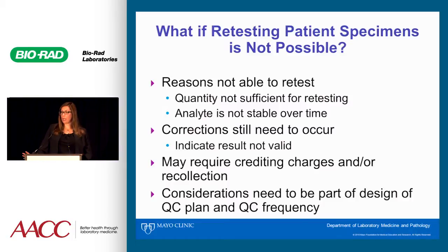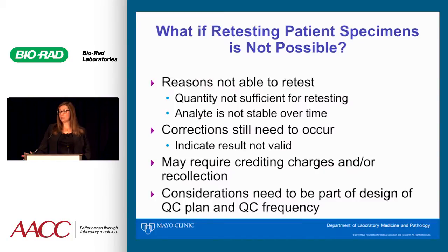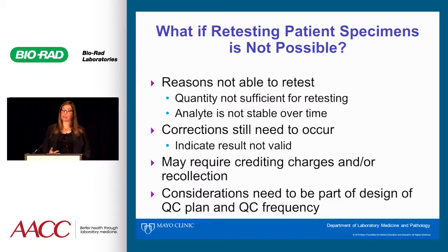I also oversee coagulation. We have a few analytes in general COAG where samples are only stable for four hours. They're pretty low-volume tests, but we need to factor in that our QC should probably be done at a frequency of every three hours, so we don't run into a problem where a sample has expired, we then catch an analytic issue, and there's nothing we can do about it.